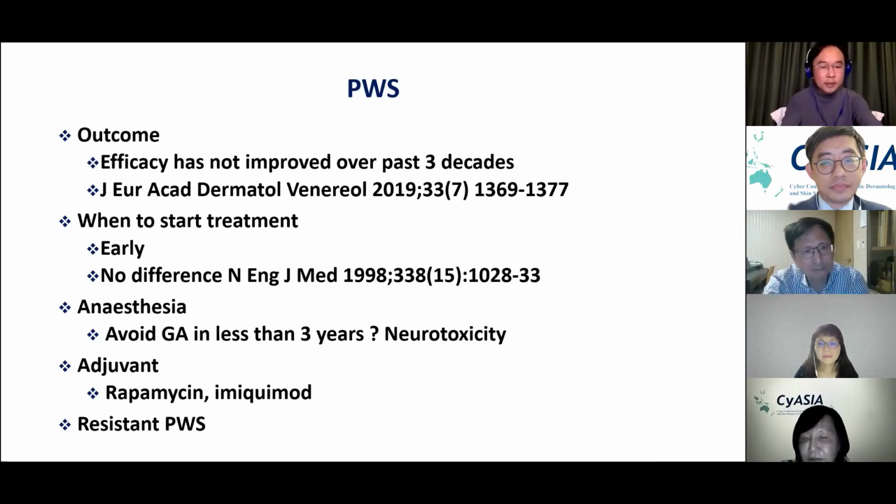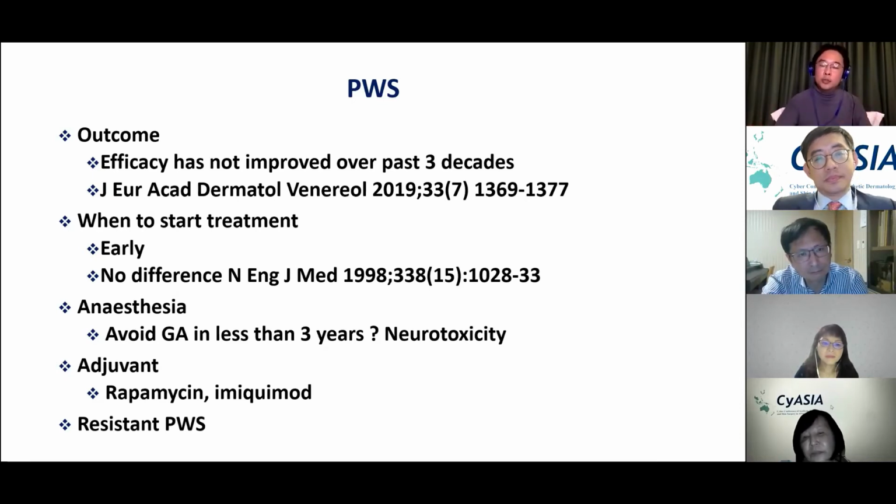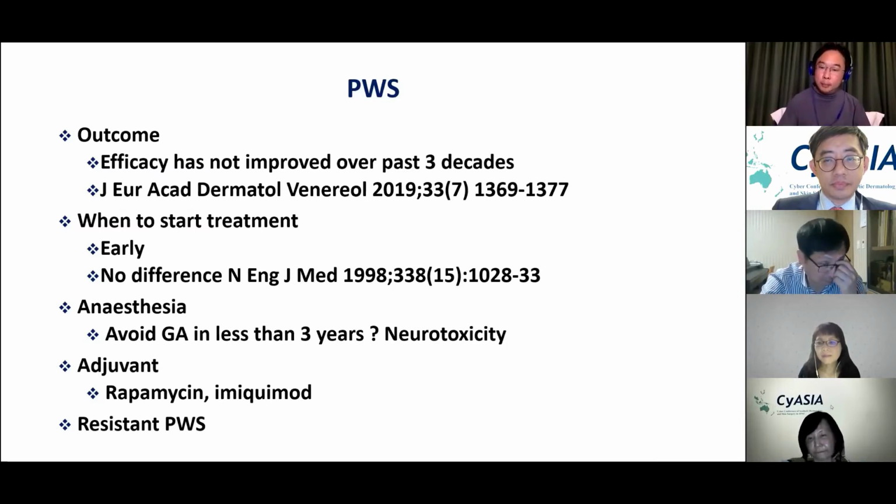Myself, it depends on the age at which I initiate treatment and how frequent. Generally, if the result is not up to my expectation, usually I will increase the spot size from 7 to 10. Of course, I don't have the 12 at the moment. Secondly, I increase the fluence until there's no blister, but yet I produce the purpuric reaction. And thirdly, I also increase the pulse duration, adjusting from 0.45 to 1.5 and sometimes to 3 accordingly.